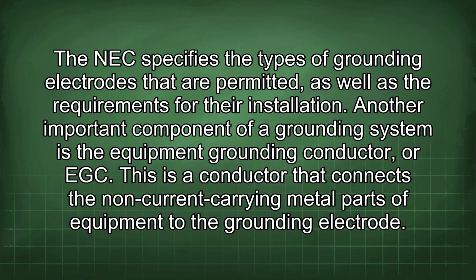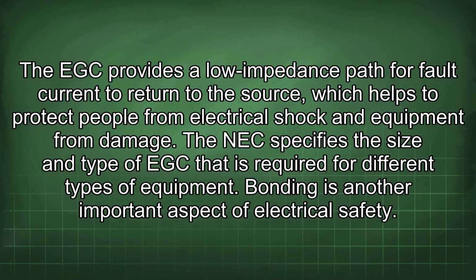Another important component of a grounding system is the equipment grounding conductor, or EGC. This is a conductor that connects the non-current carrying metal parts of equipment to the grounding electrode. The EGC provides a low impedance path for fault current to return to the source, which helps to protect people from electrical shock and equipment from damage. The NEC specifies the size and type of EGC that is required for different types of equipment.